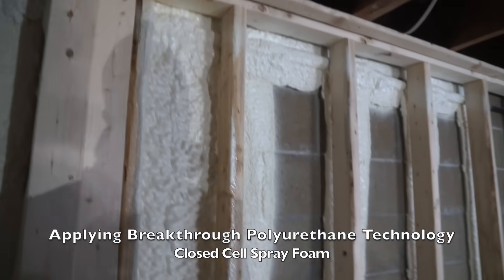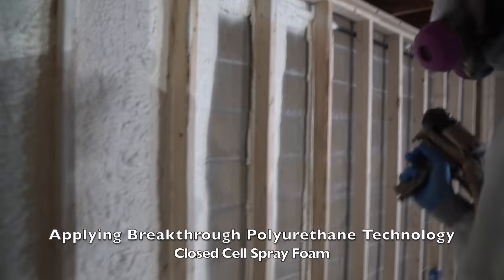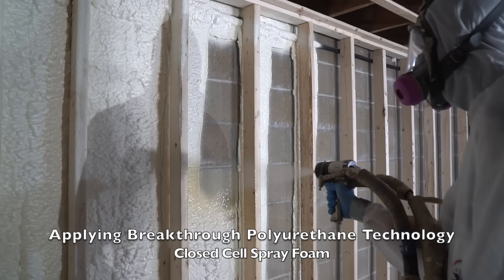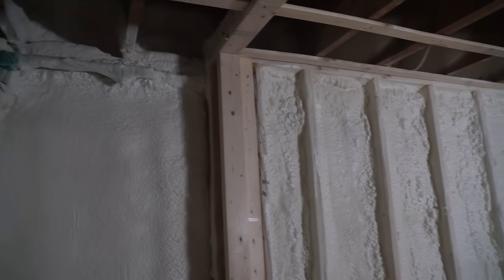The best practice here is to use closed-cell spray foam. Closed-cell spray foam is a mixture comprising of isocyanate and polyol resin, and it all comes out at the tip of an applicator. The mixture quickly adheres to the surface it's sprayed onto and rapidly expands. High-density closed-cell mixtures have a closed cellular structure that's impervious to water and air movement — a perfect vapor barrier. The foam is rigid once dry and has a fantastic R-value of about R7 per inch. Due to the closed-cell nature of the foam, it acts as a vapor barrier and will prevent humid air from condensing on cold surfaces.